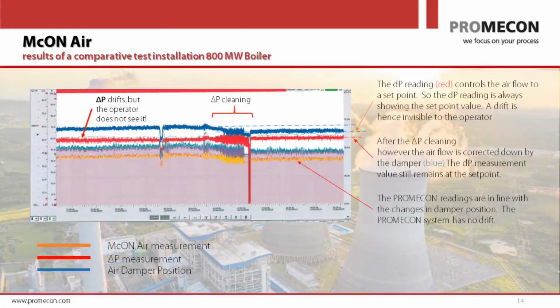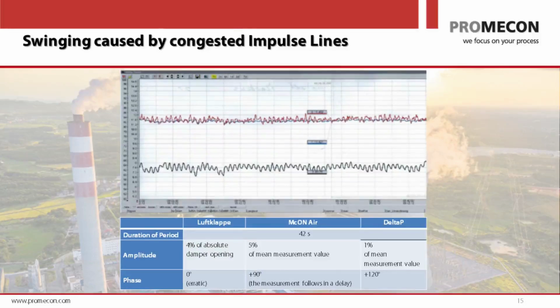So that is one of the main problems in secondary air. I would say in every boiler in this world that does not have digital airflow measurement, you will have problems with one or the other airflow measurement. There's not a single boiler without this issue. And some boilers have dozens of airflows that are not correct. Here you can also again see the typical drift, the typical problem that comes along with drift, and that's this noise. We were talking about the noise.